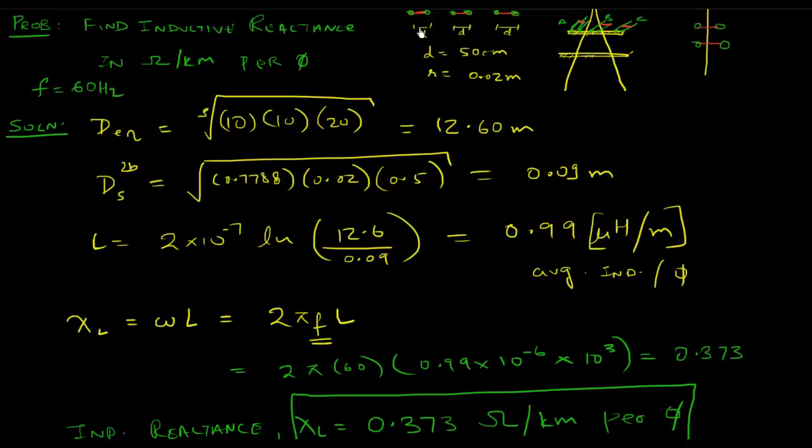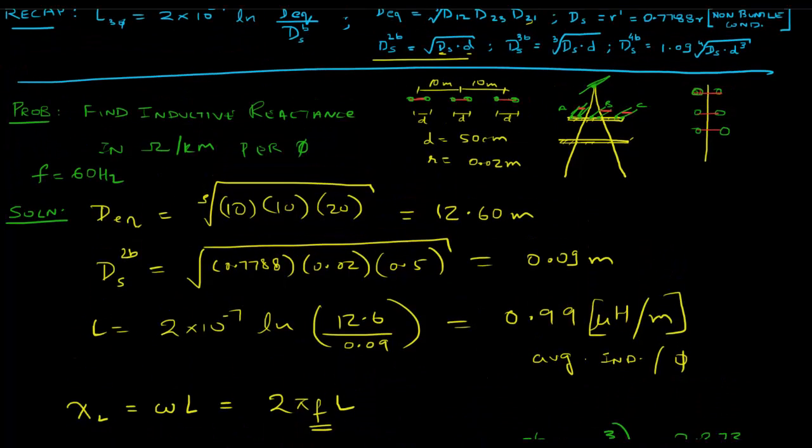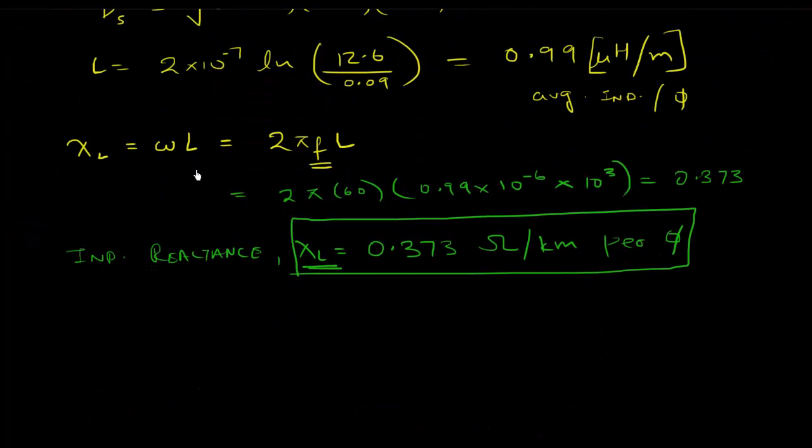Let us now, as I said, solve this using the two bundle situation. Let's just imagine it wasn't a two bundle case, it was just single conductors. Let's say it was single conductor, same distances apart. This is 10 meters, this is 10 meters. This d goes away because there's no distance between the bundles, and r was still 0.02 meters. What would the L and the XL values be in that case?